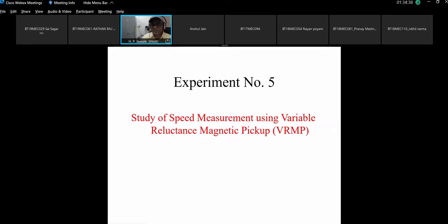Now, variable reluctance magnetic pickup is something wherein there are some magnetic flux lines produced by the transducer, and if a disc is there where there are some kind of gear teeth profiles made on that disc, and that is coming in front of the magnetic pickup flux, there will be a change in the flux density. Signals will be interrupted, and when it is received, it is going to generate a differential voltage. When a tooth is in front of it and the signals are blocked, the voltage generated by the receiver will be different than when it is in front of the clear passage. The magnetic flux line collector will have higher density, so that higher voltage is induced. So it will be high volt, low volt for each tooth that is coming in front of the receiver.